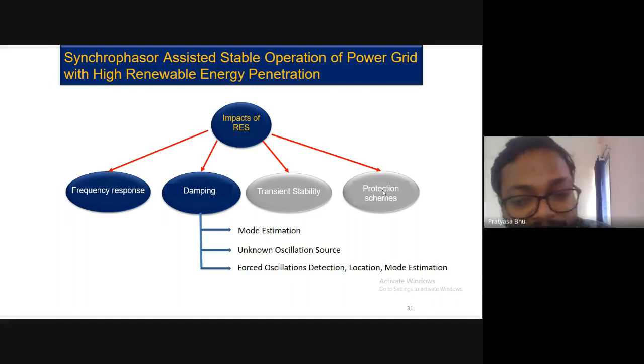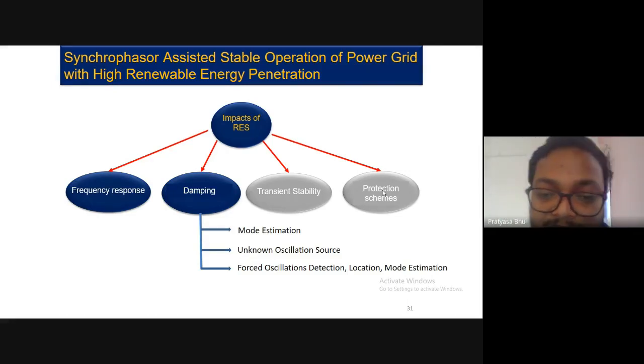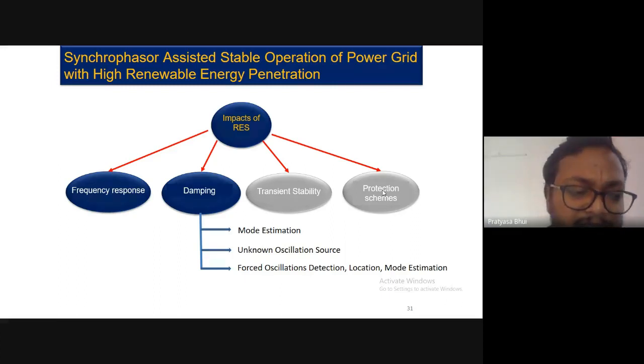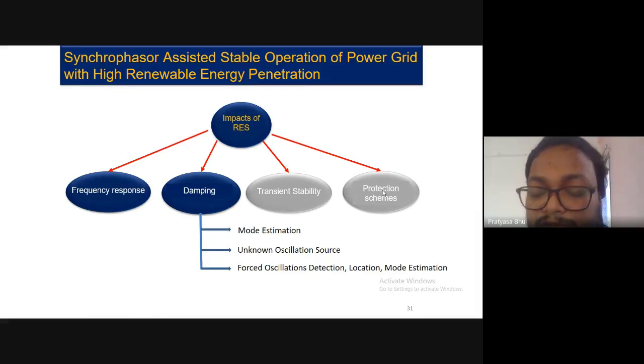Suppose a spring mass system. Without any controller, the oscillations will never grow. There will be inherent damping present, and it will damp out the oscillations. But if there is continuously an external input to one mass, it is causing oscillations. So how to identify which generator is causing those oscillations? There is a difference between forced oscillations and natural oscillations. Natural oscillations are inherently present in the system dynamics, and you find the eigenvalues. When the damping is poor, it causes oscillations. Forced oscillations are not because of the system, but because there is some error in the controllers giving continuous error signals to the reference.